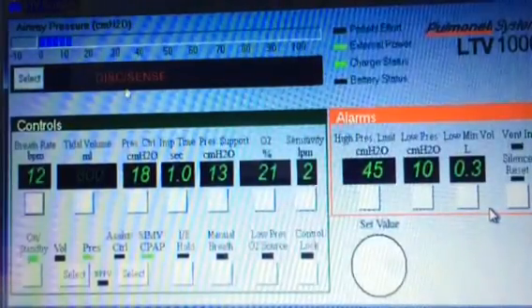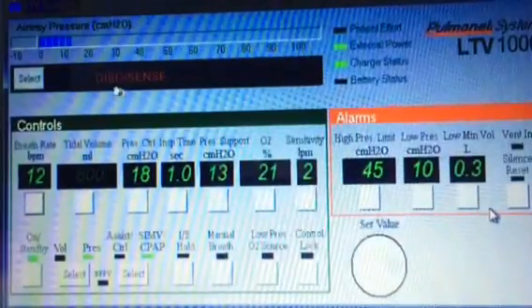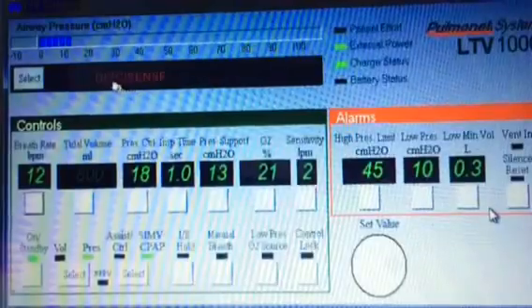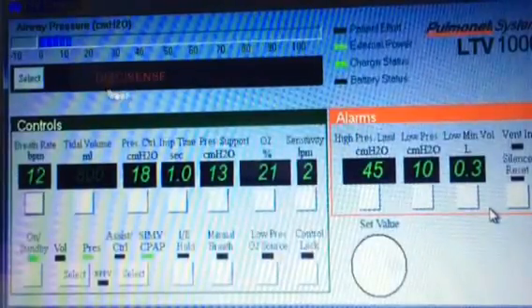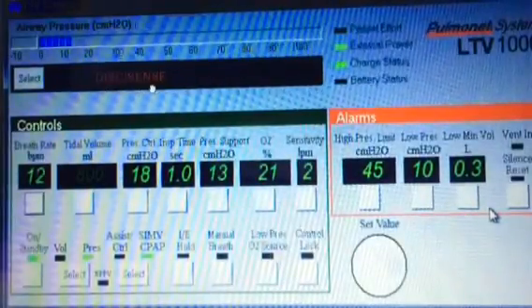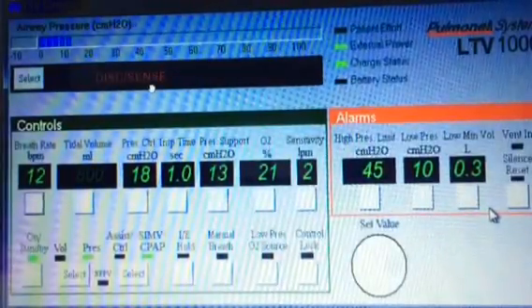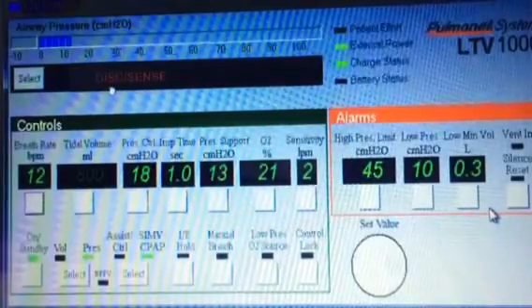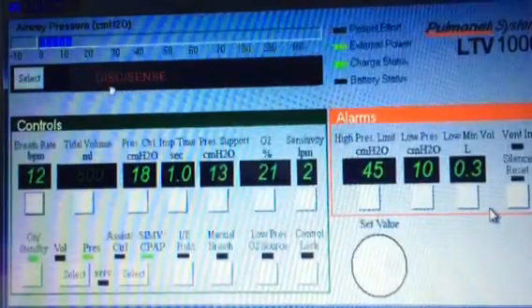If you are wondering what the Disc Sense Alarm means, it tells you right in the wording of it. The tubing is either disconnected, or the Sense tubes are occluded. It's that simple. Those are the two things you need to check for, and in the order that you need to check for them.